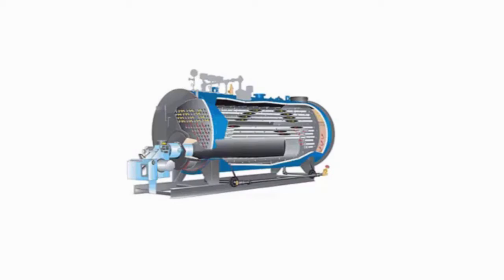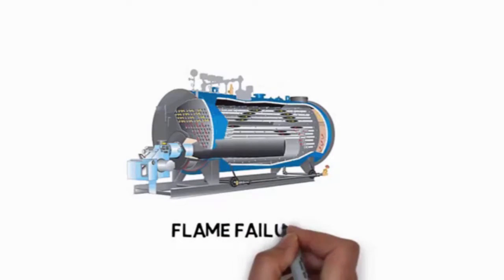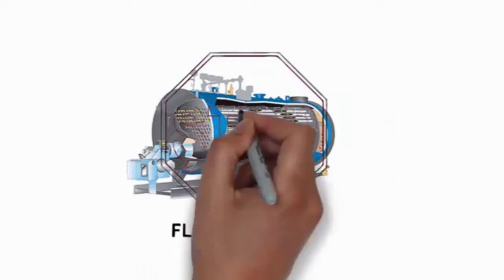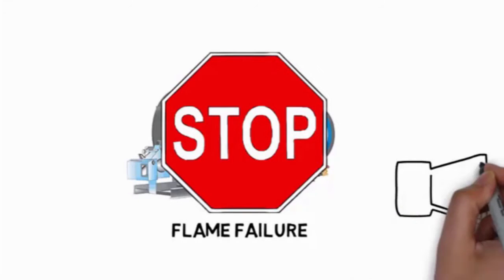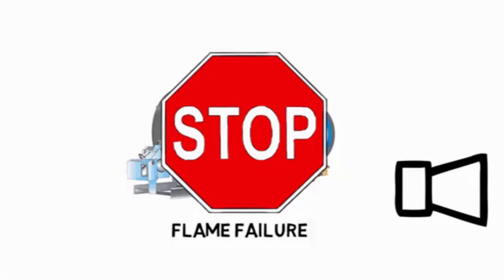If there is a flame loss or inability to maintain a stable flame after the flame establishment period has elapsed, a lockout will occur. The alarm relay is used to annunciate a lockout condition.